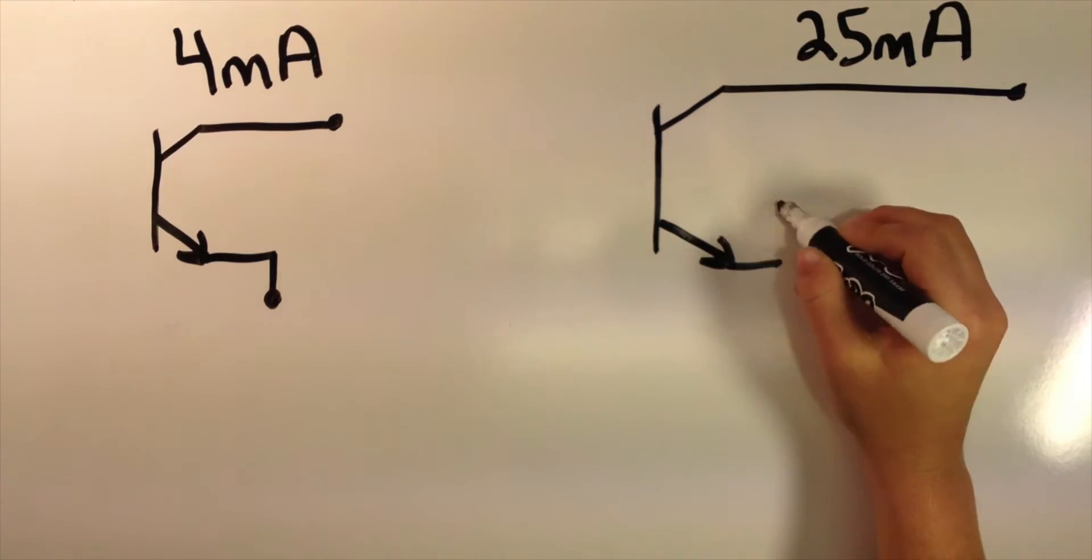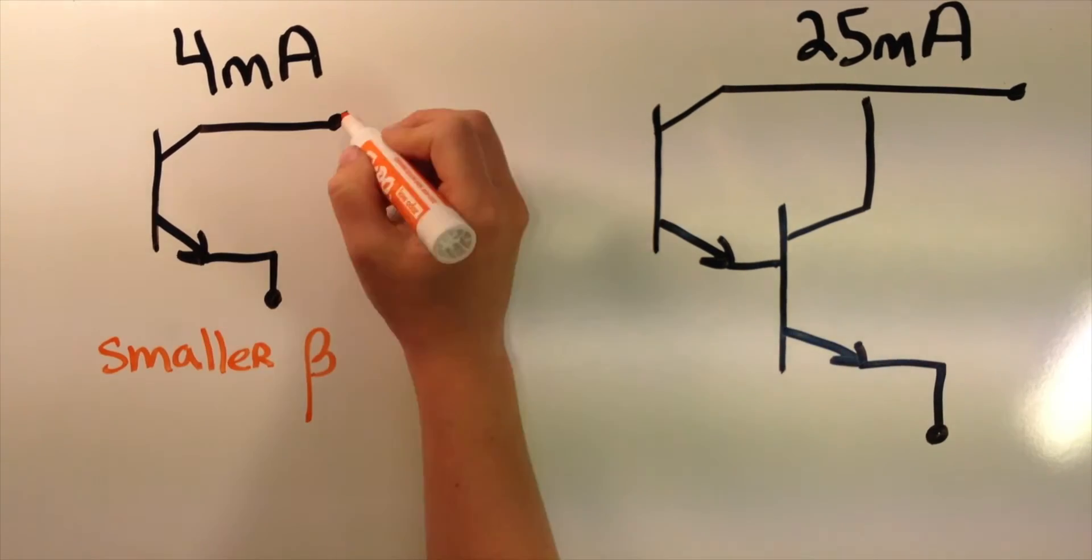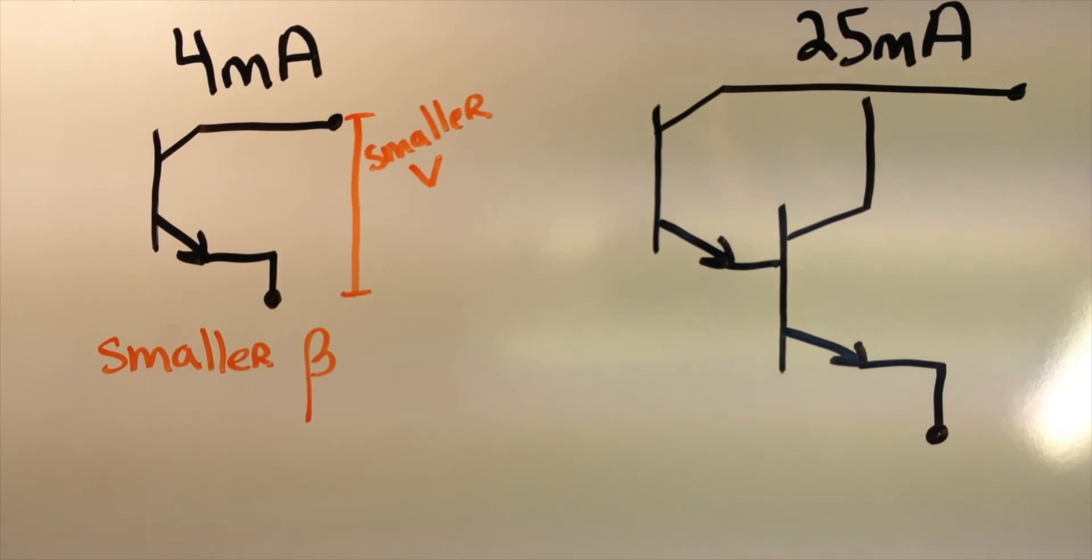The 25mA option in comparison uses a Darlington pair. The transistor used in the 4mA has a lower current gain and a smaller voltage drop across it, whereas the 25mA sink sourcing options have a higher current gain and a larger voltage drop.